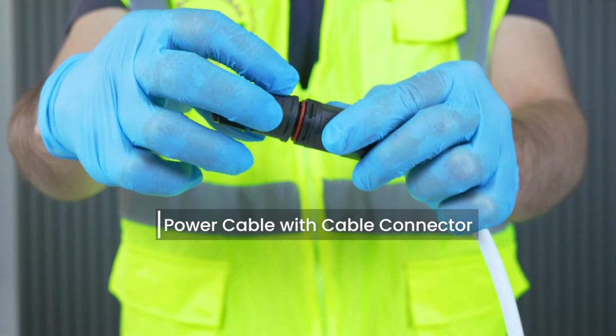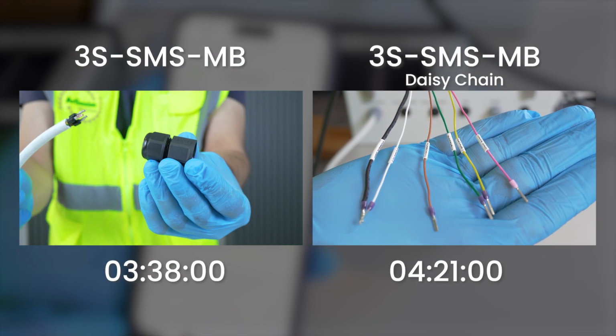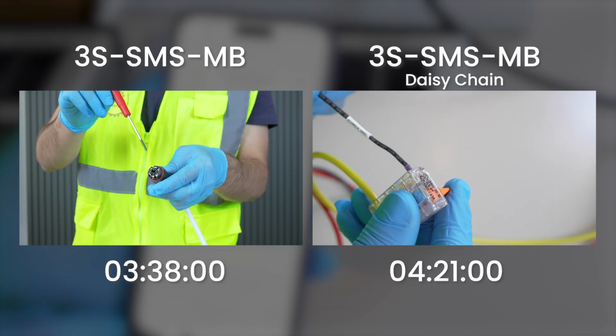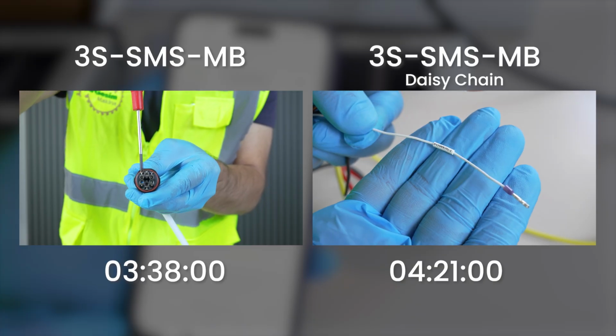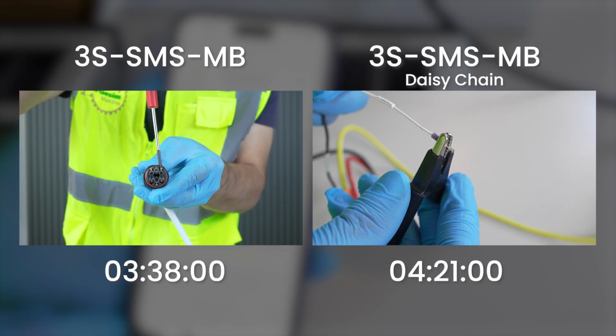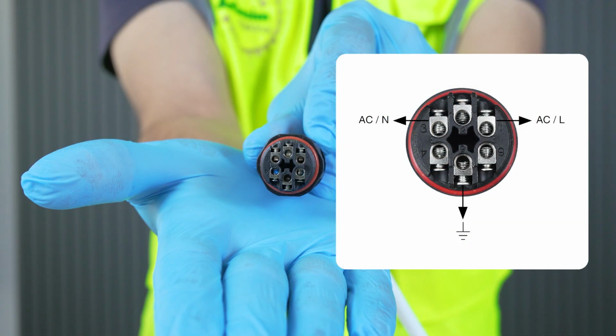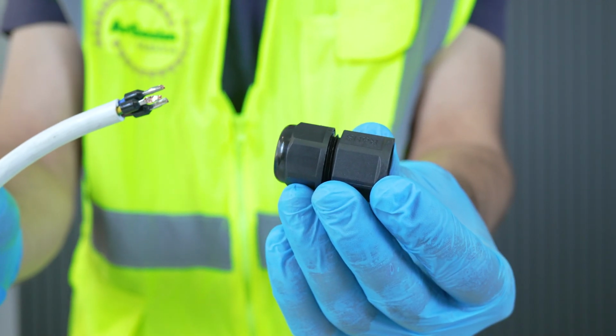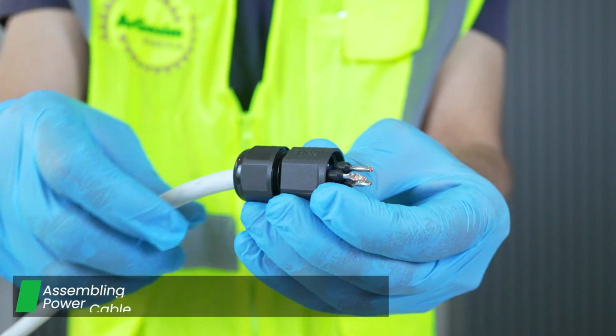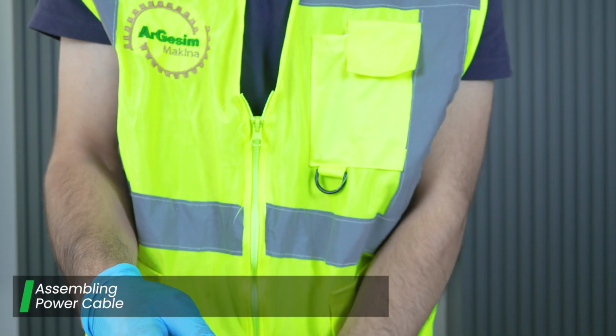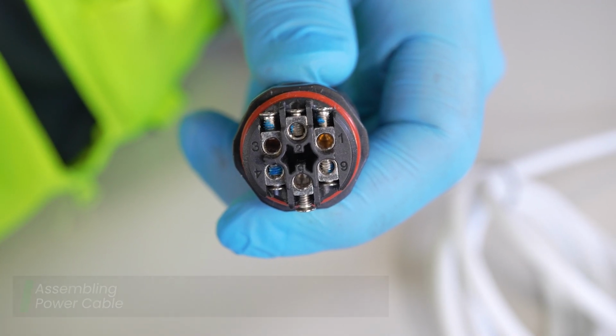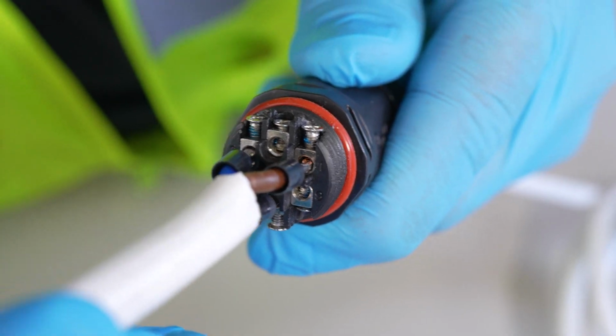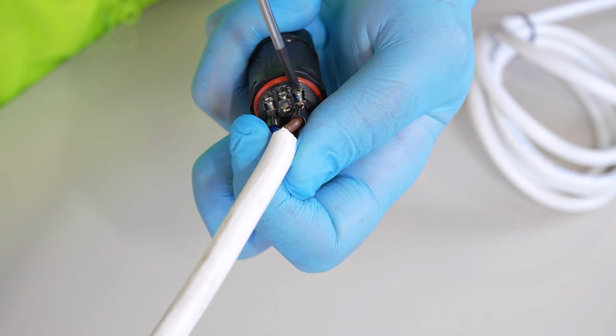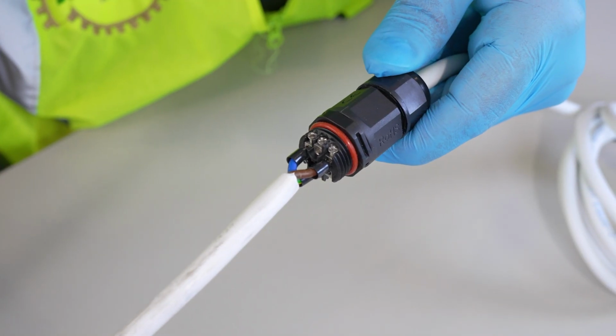Now, connect the sensor to the power supply. There are 2 types of soiling sensors, the standard model and the daisy chain model. If you have the standard model, keep watching, but skip the section from 338 to 421. If you have the daisy chain model, jump straight to 421. If you have the 220-volt AC model, connect line to terminal 1, ground to terminal 5, neutral to terminal 3. Then secure and reseal the gland.